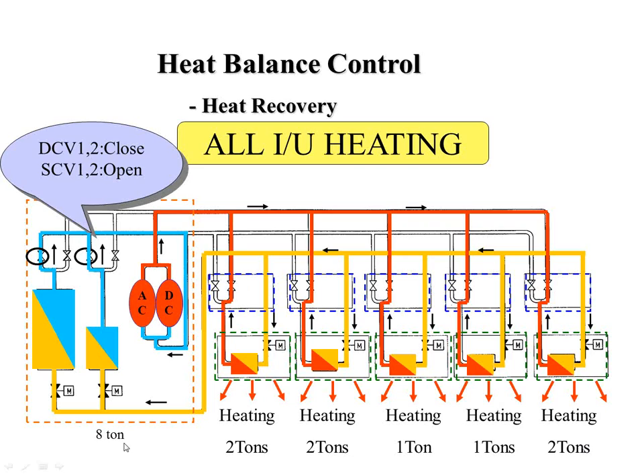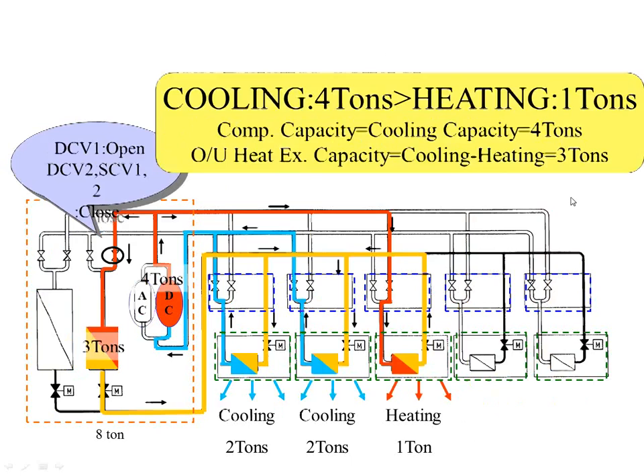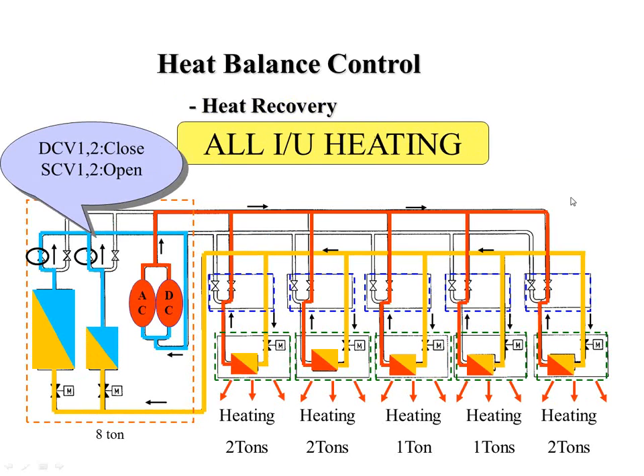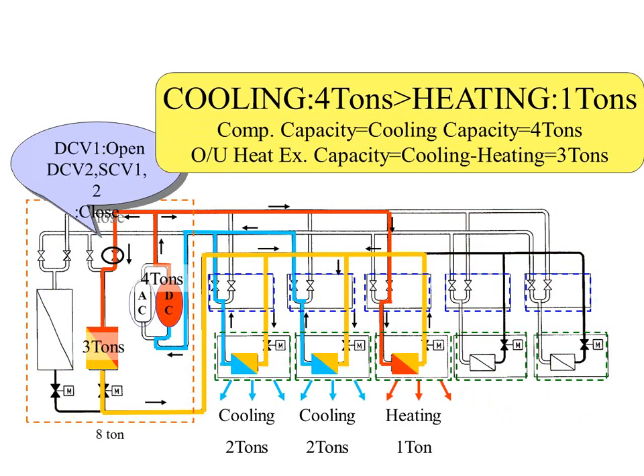That's very common, right? Just like with a VAV system, we take advantage of the diversity credit. Every single zone doesn't need max heating and max cooling at the exact same moment in time, so we can take some diversity credit. Actually, this time we didn't do that. We have 8 tons on 8, so we could have done that. We should have used a 6-ton unit probably. But what happens here, everybody's in heating mode, so all the indoor units are condenser coils, and the outdoor unit is the evaporator coil.